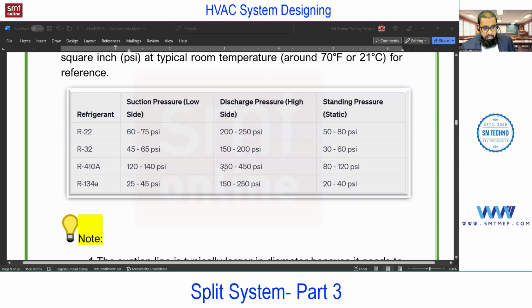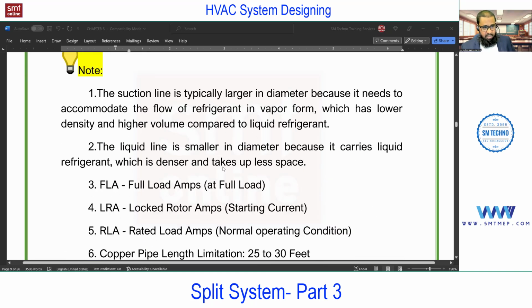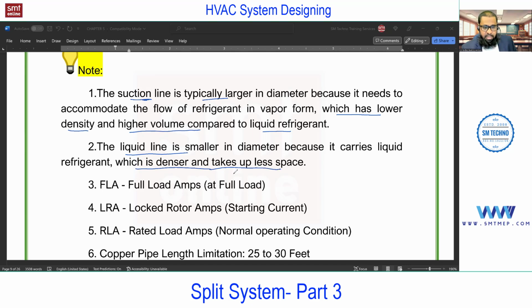Next, apart from this, some more important points. What I explained, the suction and discharge line, why the difference in diameter? You see, the suction line is typically larger in diameter. The reason is what? You see, vapor has lower density and higher volume compared to the liquid refrigerant. And the liquid line is smaller. The reason is, you see, density is higher and less space is required.